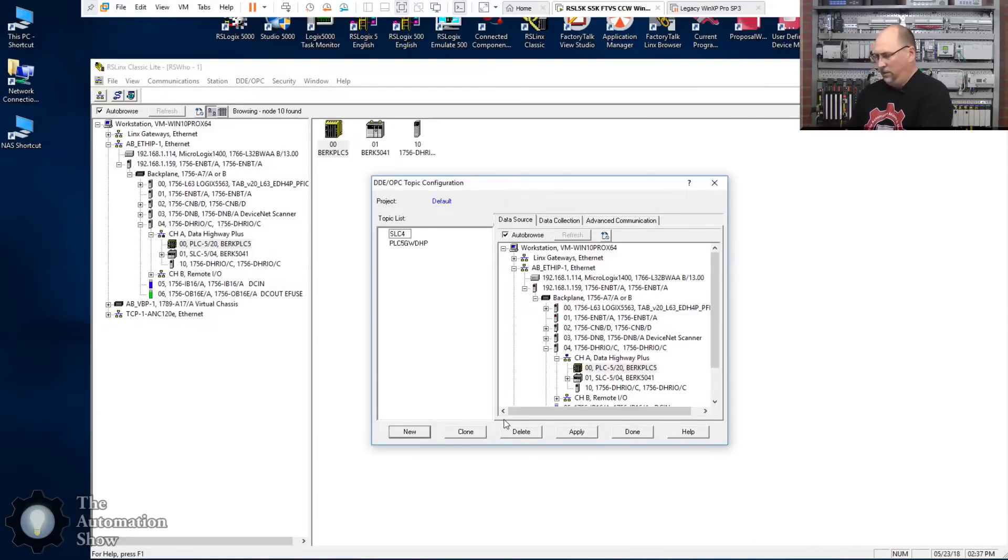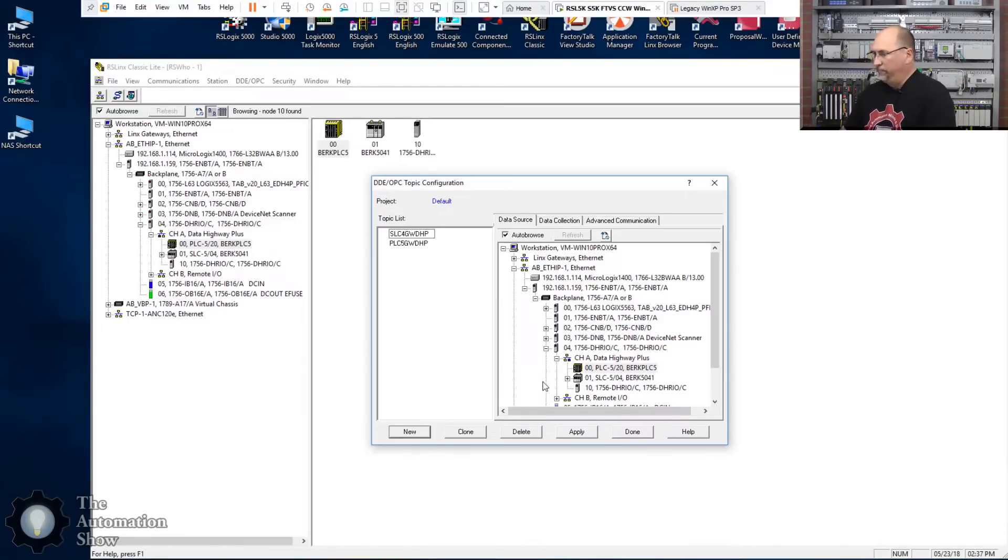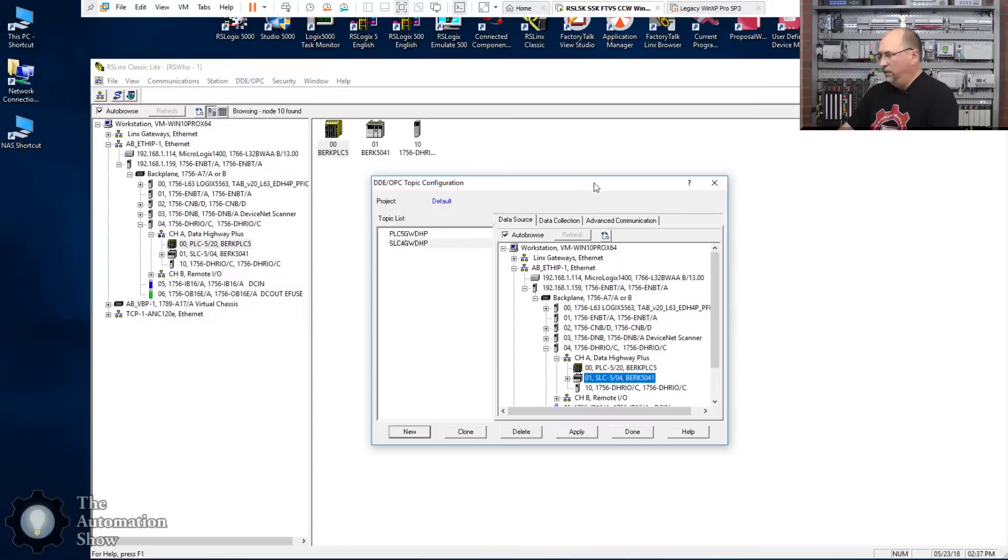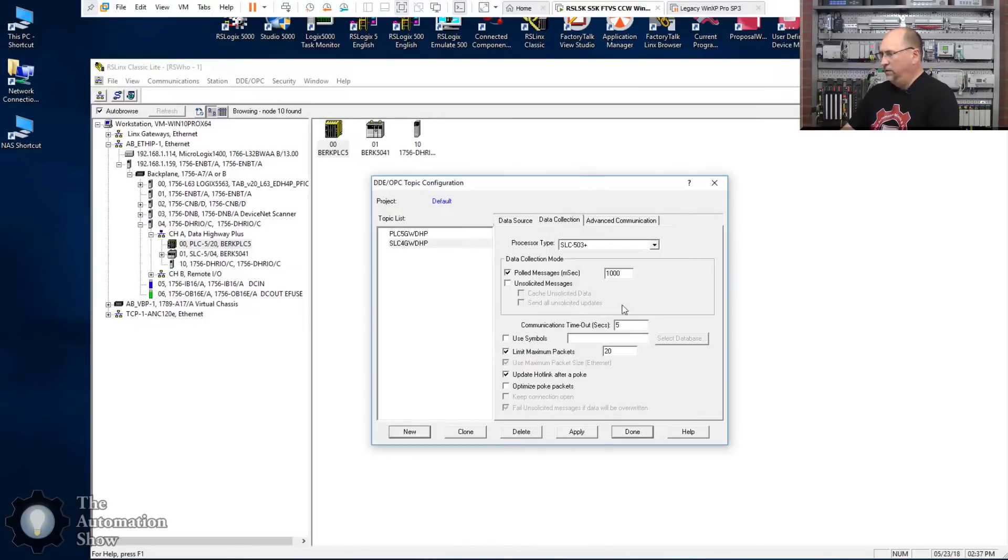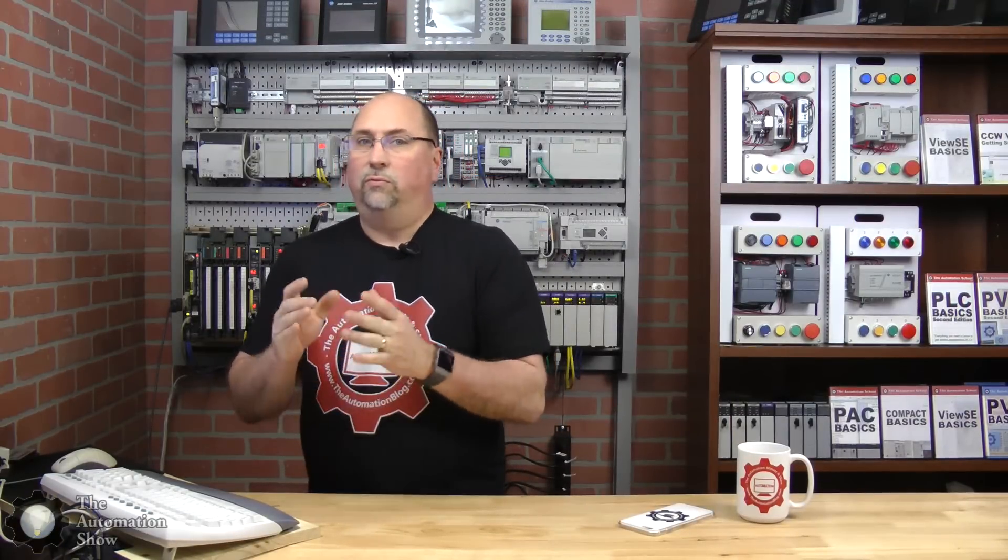Let's go ahead and add another one. This one time we'll create it manually. SLC, I'll call it SLC4_Gateway_DHP. Okay, and I'll select the controller here, go to data collection, speed it up to—I wouldn't go any slower than 250 milliseconds unless you have a really, really loaded down Data Highway Plus.